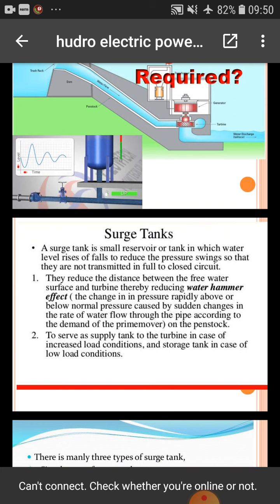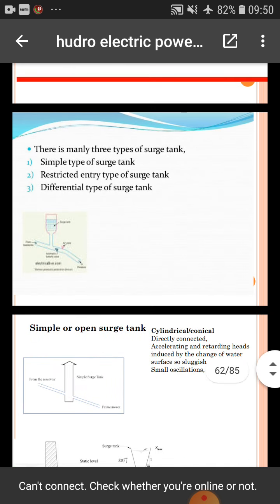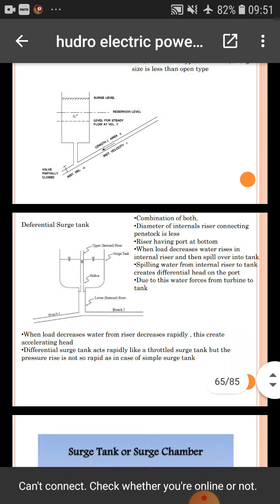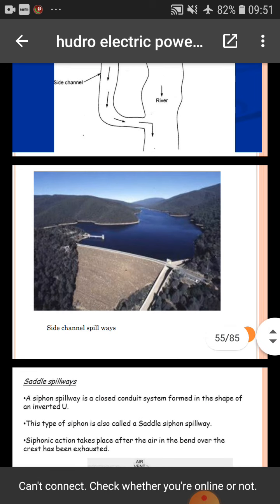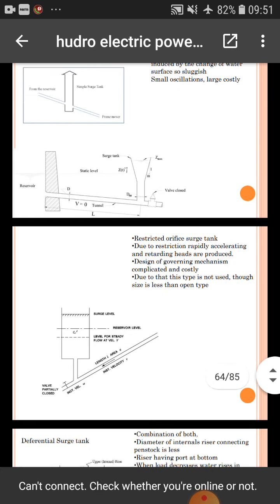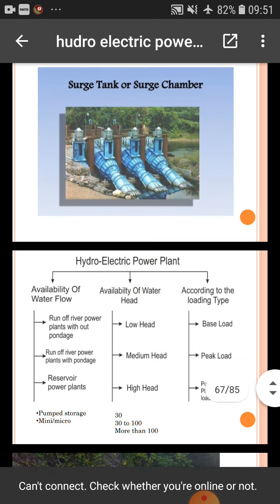Surge tank: a surge tank is a small reservoir or tank in which the water level rises or falls to reduce pressure swings so they are not transmitted in full to the closed conduit. They reduce the distance between the free water surface and the turbine, thereby reducing the water hammer effect. The simple open surge tank is cylindrical or conical and is directly connected to the penstock. It produces accelerating and retarding heads induced by change of water surface. A photograph of the surge tank or surge chamber is shown.